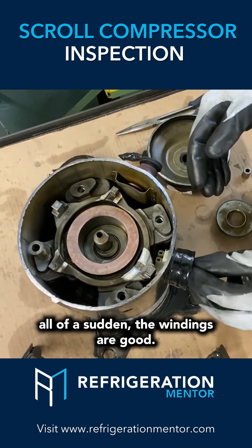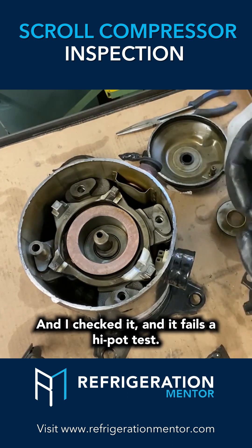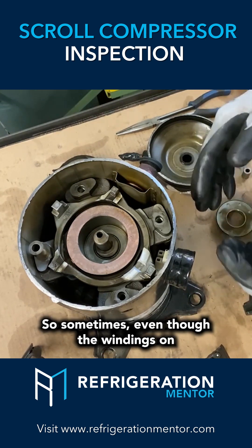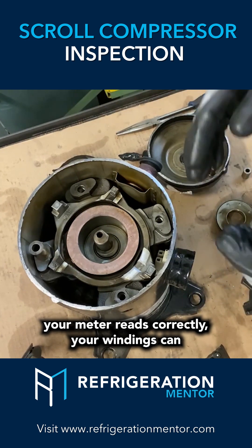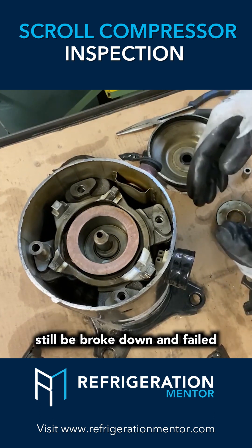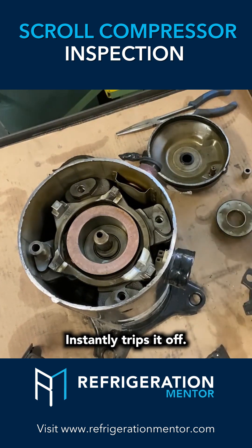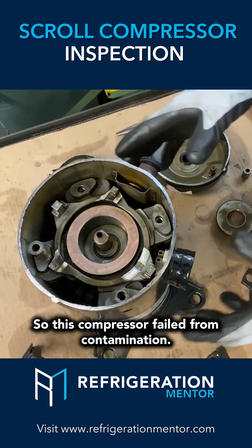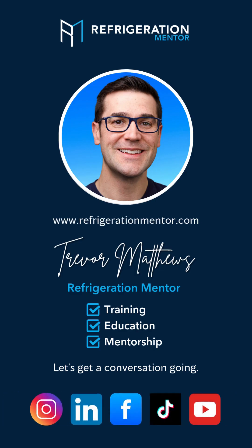If you get a compressor like this and all of a sudden the windings are good, check it with a hi-pot test. I checked it and it fails a hi-pot test. Sometimes even though the windings on your meter read correctly, your windings can still be broken down and failed — instantly trips it off. So this compressor failed from contamination.